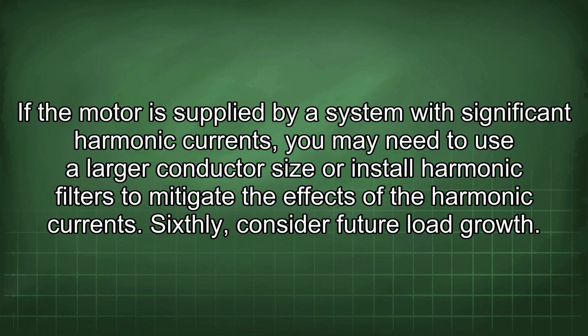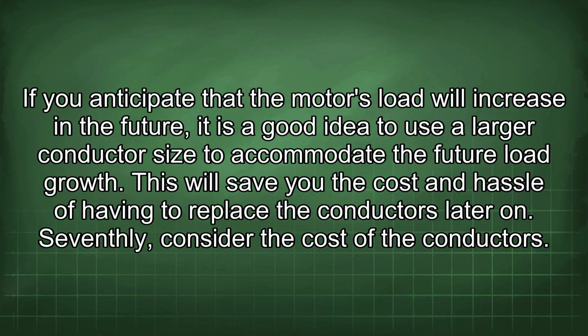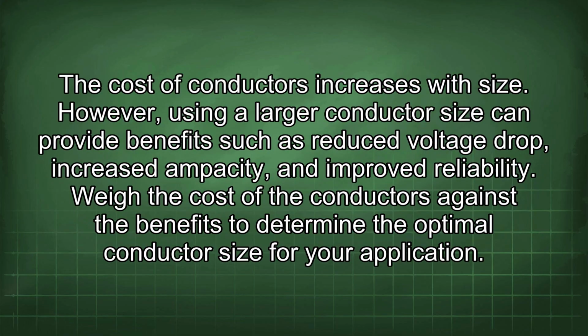Sixthly, consider future load growth. If you anticipate that the motor's load will increase in the future, it is a good idea to use a larger conductor size to accommodate the future load growth. This will save you the cost and hassle of having to replace the conductors later on. Seventhly, consider the cost of the conductors. The cost of conductors increases with size. However, using a larger conductor size can provide benefits such as reduced voltage drop, increased ampacity, and improved reliability. Weigh the cost of the conductors against the benefits to determine the optimal conductor size for your application.